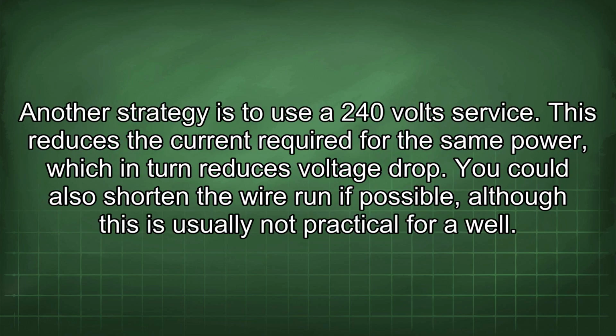Another strategy is to use a 240-volt service. This reduces the current required for the same power, which in turn reduces voltage drop. You could also shorten the wire run if possible, although this is usually not practical for a well.